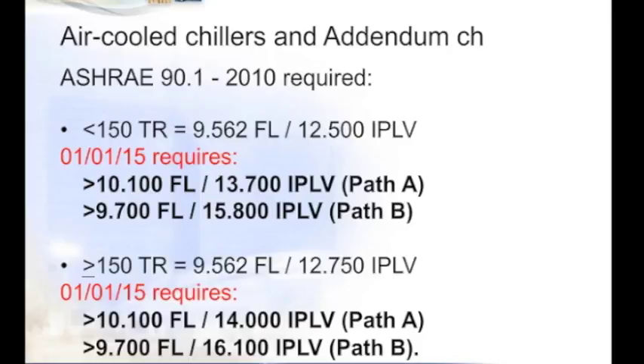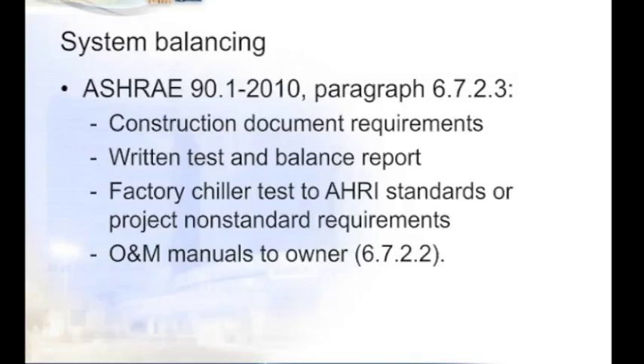Thanks, Jason. One of the requirements of ASHRAE 90.1 2010 in paragraph 6.7.2.3 includes the requirements for system balancing. Even though it's not specifically part of addendum CH, which just focuses on the water chilling equipment, it's important to note that this equipment is part of the system and must be balanced to its design conditions, whether the conditions are AHRI standard conditions or non-standard conditions. The other thing is when you prepare project documents, construction documents or written specification requirements, that it must identify the requirements and include the requirement for a written test and balance report, operation and maintenance manuals, and perhaps a verified or certified factory test of the chiller to prove that it meets the project design requirements, the required efficiency, and is properly labeled. Labeling is another item that is specifically required by 90.1.